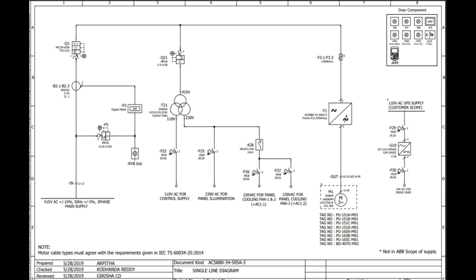Next, this control transformer further gives two different voltage levels. One is 110 volt and this will go to the F22 MCB, which is used for control supply, we will see that ahead. Another is 230 volt output, and there you can see the first tapping is for the F25 MCB, and that is used for panel illumination.